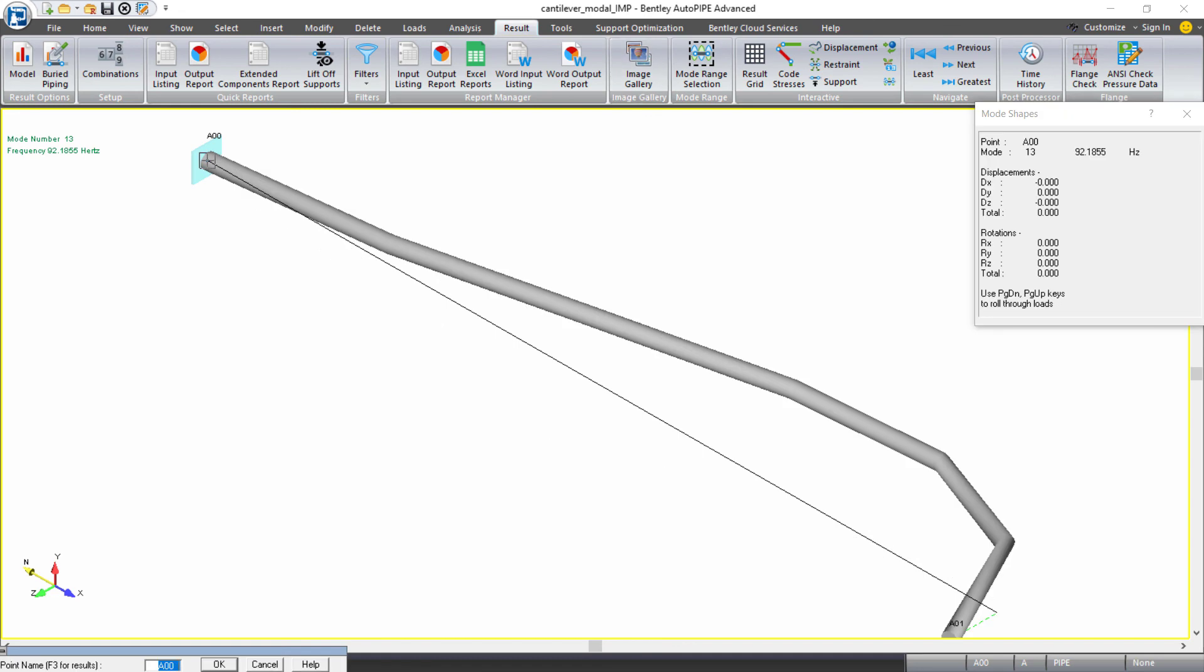Keep in mind that this is the same exact model that we used in the very first exercise, where we only obtained two modes. The program has split this 49.21 foot length into much shorter spans, which makes it possible to calculate all of the natural frequencies up to the 100 hertz cutoff. And our frequencies are also much nearer to our predicted values from the Roark calculation. So let's go back to the presentation one more time to summarize our findings and learn a bit about static correction methods.